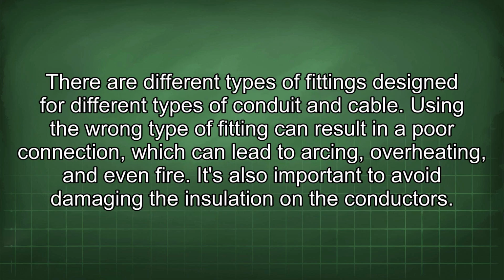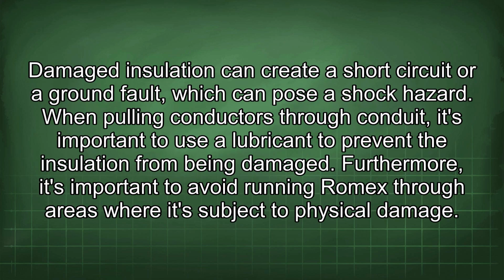There are different types of fittings designed for different types of conduit and cable. Using the wrong type of fitting can result in a poor connection, which can lead to arcing, overheating, and even fire. It's also important to avoid damaging the insulation on the conductors. Damaged insulation can create a short circuit or a ground fault, which can pose a shock hazard. When pulling conductors through conduit, it's important to use a lubricant to prevent the insulation from being damaged.